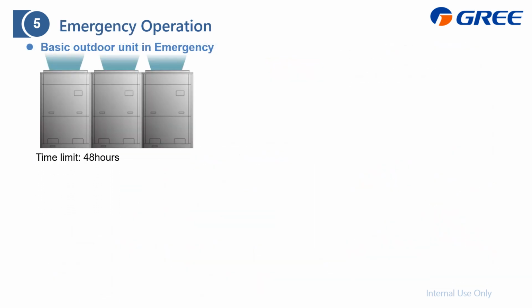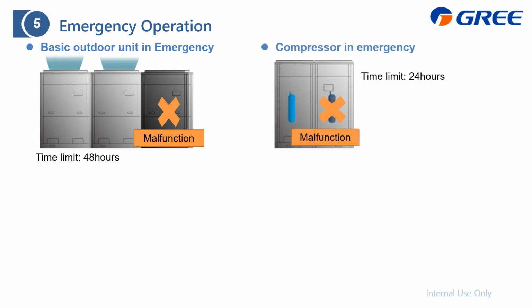Emergency operation. For this one, we have the emergency operation for the whole outdoor unit, which means if there's something wrong with it, you still need some time to prepare the material to do the repair, and we allow this system to still operate, and you can apply this to shield this unit off. The time limit for this is 48 hours. And for the compressor, it is also allowed to shield it off, only for an outdoor unit with two compressors inside. The time limit for this is 24 hours.